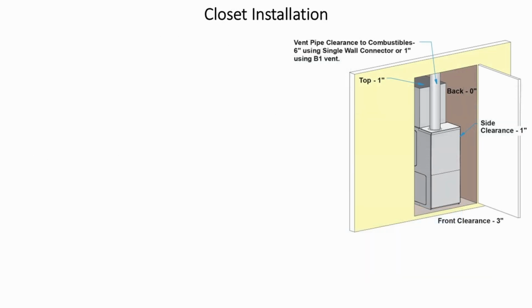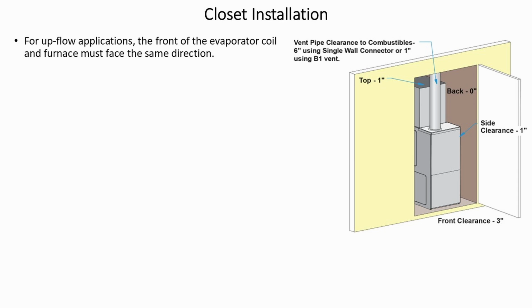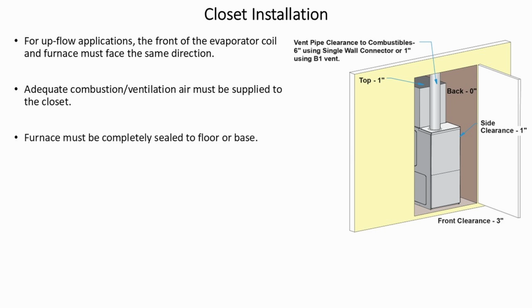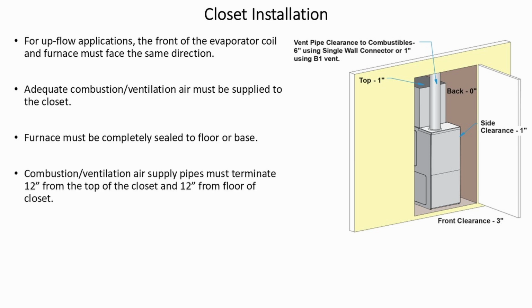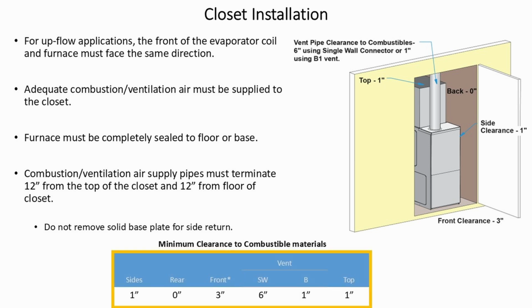Closet installations. For upflow applications, the front of the evaporator coil and the furnace must face the same direction. Adequate combustion and/or ventilation air must be supplied to the closet. Furnace must be completely sealed to the floor or base. Combustion and/or ventilation air supply pipes must terminate 12 inches from the top of the closet and 12 inches from the floor of the closet. Do not remove solid base plate for side return. Below, see the chart for minimum clearance to combustible materials.